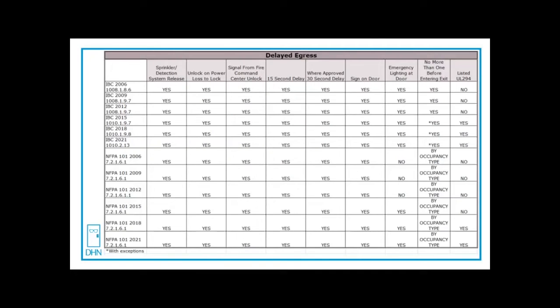As you can see from that short video, delayed egress is locking the door on the egress side. Only for 15 seconds unless by exception where you can have up to a 30 second delay.